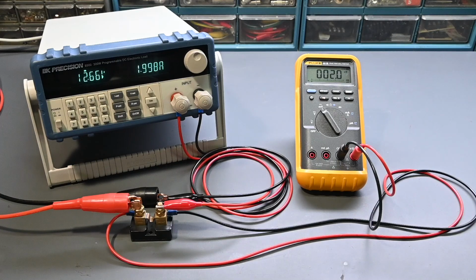Now again, like before with the digital multimeter's internal shunt, with this system you have to physically break into the circuit for the measurement. That's exactly how I have things set up here, and I'll explain that in just a moment. And the accuracy depends on the shunt resistance tolerance and the tolerance of the voltmeter being used. And there is some voltage drop on the shunt necessarily, and the shunt adds series resistance to the circuit, but it's negligible in most cases. And as before with the digital multimeter and the analog meter, the Simpson 260, the shunt resistance goes up as the current measuring ranges go lower.